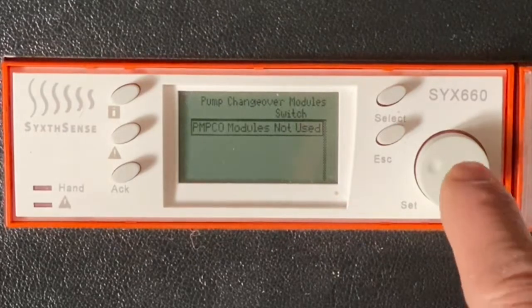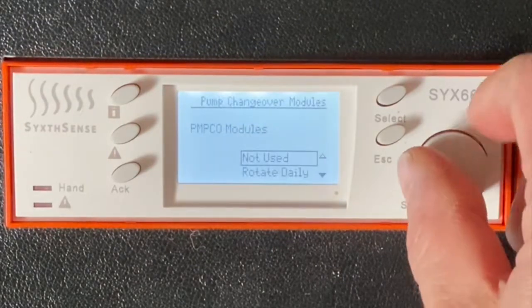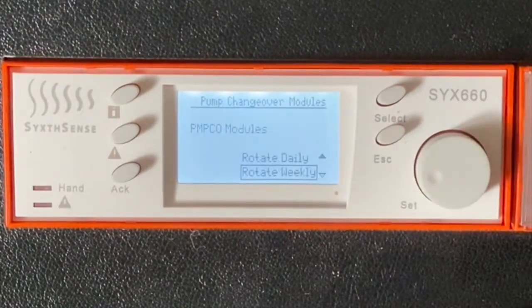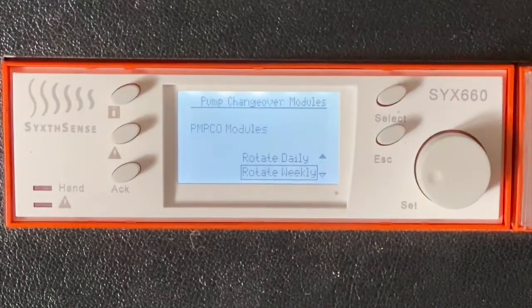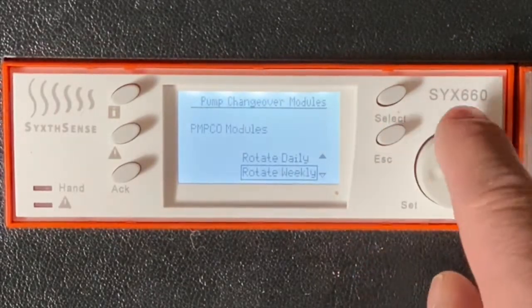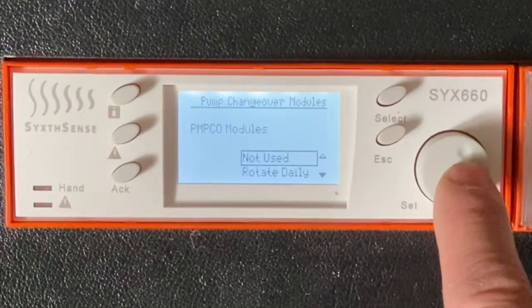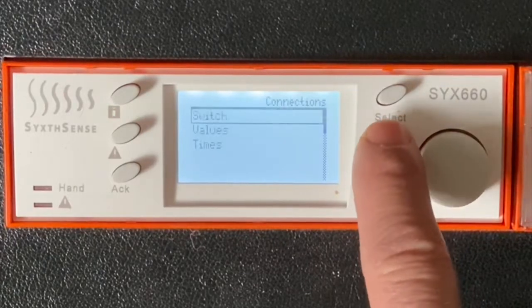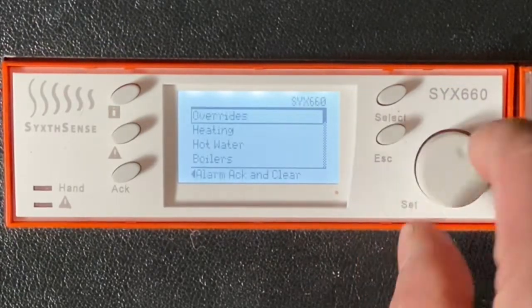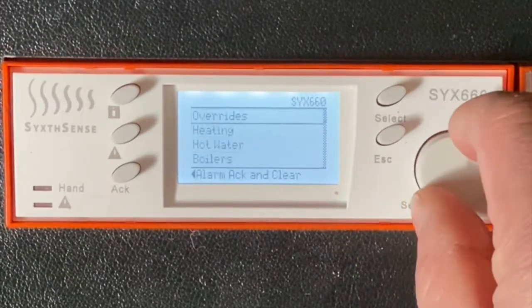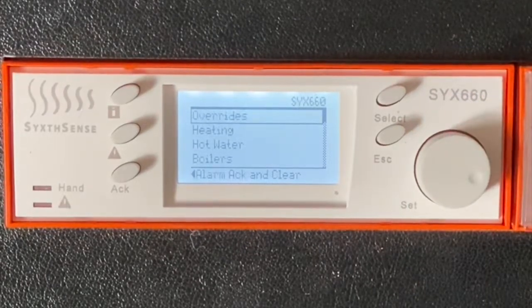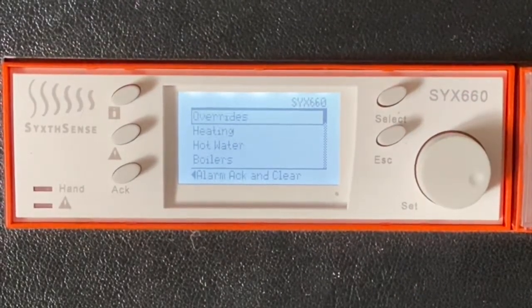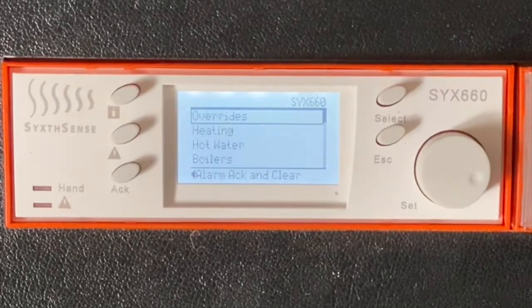Okay, so that's what the pump changeover module menu will do. It will allow us to rotate weekly or daily, and that's what it does. It disrupts the pump demand signal for 15 seconds so that the pumps can change over. We're going to be leaving that not used at the moment. Okay, so that concludes all of the menus that we need for the setup mode. So what I'd like to do now is take the opportunity to show you a few things that the controller can be used for in terms of helping you to commission the product.